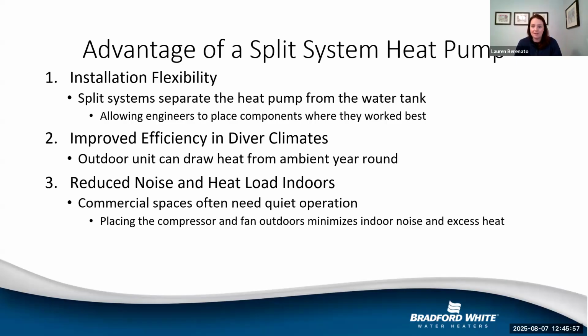Improved efficiency in diverse climates. The outdoor unit can draw heat from ambient air year-round, which is a huge advantage, optimizing performance even in the cooler months. Keeping the water tank indoors helps maintain water temperature stability, so that reduces standby loss. And then also reduce noise and heat load indoors. Commercial spaces often need quiet operation and controlled indoor climates. So by placing that compressor fan outside, it will minimize your indoor noise as well as excessive heat.